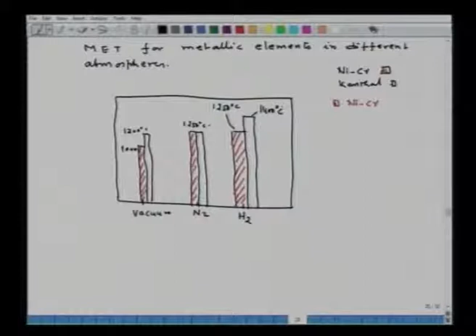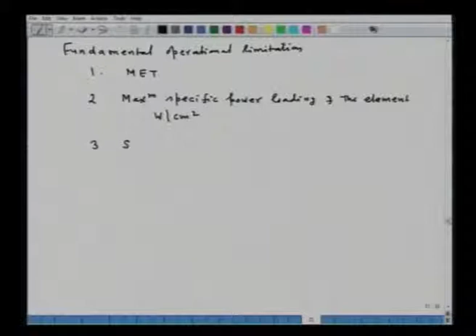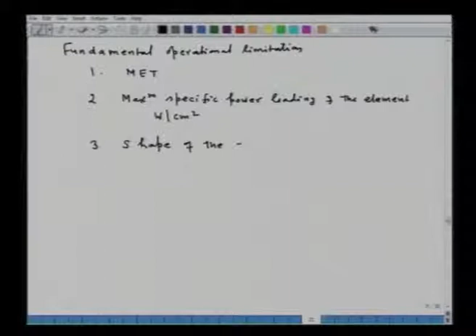So, the fundamental operational limitations are: Number 1, maximum element temperature. The maximum element temperature should be greater than the temperature required, or the temperature of the furnace. Second, maximum specific power loading of the element, that is in watt per centimeter square. That will decide the watt loading. And the third important thing is the shape of the element. What shape are you going to select?